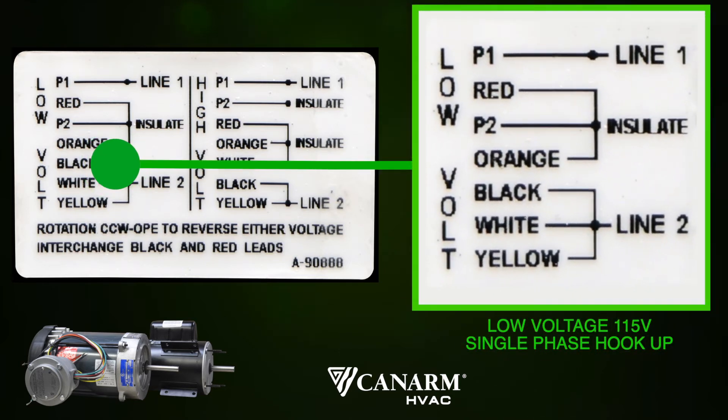Line 1 and line 2 will refer to your leads. Insulate will refer to capping off with a wire nut or a Marrette. P1 motor lead is connected to line 1, your hot. Black, white and yellow motor leads are twisted together and connected to line 2, your neutral. This leaving the red P2 and orange to be twisted together and capped off with a wire nut or marrette.